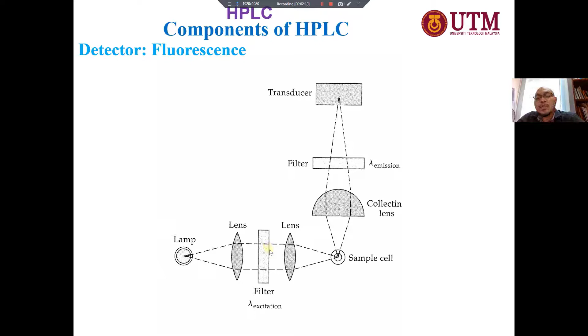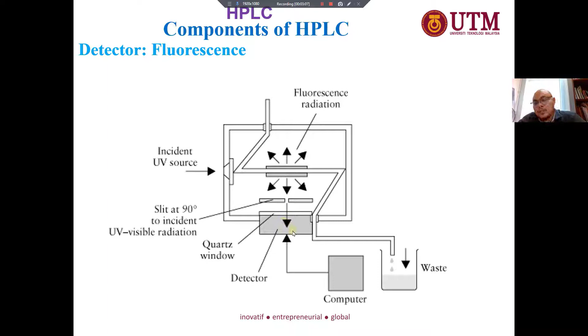Okay, this is the schematic diagram of the detector. Here is the incident, here is the flow of the eluent. We direct the UV source to the sample, and then the detector is at a 90 degree angle. In the normal UV we put it here, right? But for fluorescence, we put it at a 90 degree angle, because we want to measure the light fluoresced by the sample.